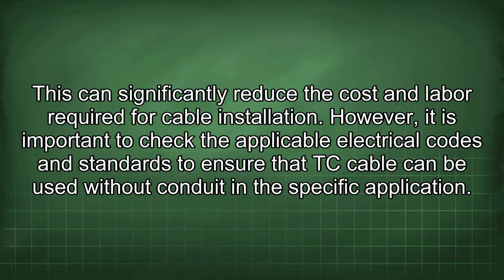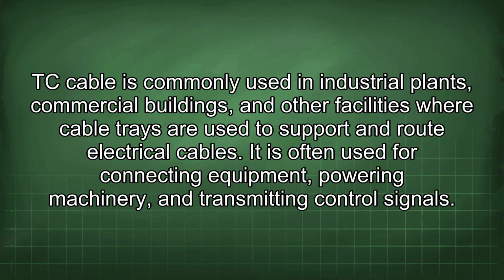This can significantly reduce the cost and labor required for cable installation. However, it is important to check the applicable electrical codes and standards to ensure that TC cable can be used without conduit in the specific application. TC cable is commonly used in industrial plants, commercial buildings, and other facilities where cable trays are used to support and route electrical cables. It is often used for connecting equipment, powering machinery, and transmitting control signals.